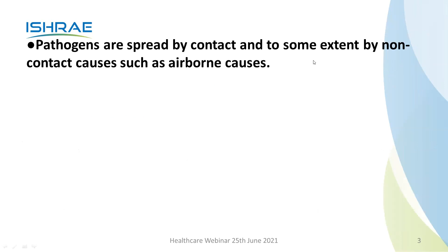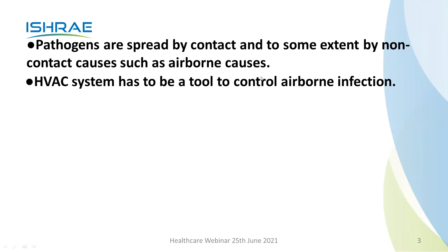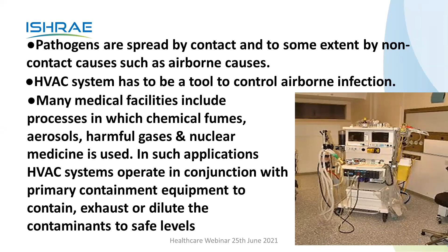Pathogens are spread by contact and to some extent by non-contact causes such as airborne causes. HVAC system has to be a tool to control the airborne infection. Many medical facilities include processes in which chemical fumes, aerosols, harmful gases, nuclear medicine is used. In such applications, HVAC systems operate in conjunction with primary containment equipment to contain, exhaust, or dilute the contaminant. What is containment? It means by means of pressure or by means of some barriers, you don't allow the harmful gases to go out of that particular area.